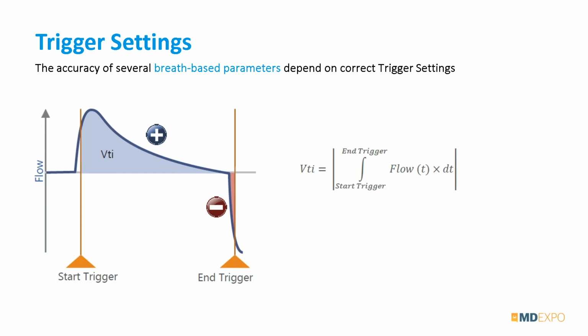So in this example shown here on the screen, if my trigger settings are off in timing, it means that in reality the breath starts here, but I'm actually being triggered too late. And on the other side, my inspiratory phase ends here, but my trigger also triggers too late. Then I miss a certain volume in my calculation, right? And on the other side, here it goes negative into exhalation, and I calculate a little bit of this negative flow still in my inspiration. So as you can imagine, the tidal volume calculated by my gas flow analyzer is then going to be quite a bit off, right? So the trigger settings also have an impact on the accuracy of my measurements.